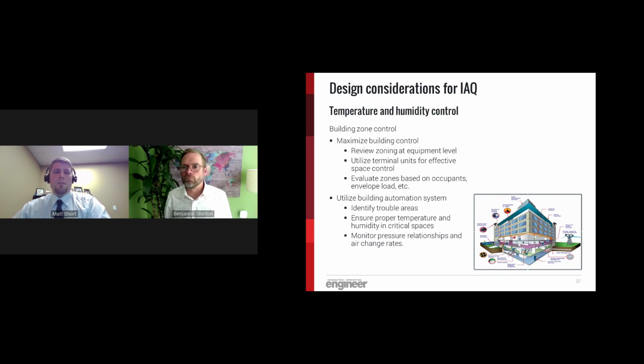At the zone level, it's also important to maximize zone level control and isolate spaces with varying occupant loads or uses. Review your zoning at an equipment level and be sure to combine similar spaces on a common distribution system to prevent load swings. Try to utilize terminal units where applicable to allow for effective local zone temperature control, and discuss with the building owner the intent for each space so that you can fully understand the load profile for each zone. It's also important to utilize the building automation system to help with zone control.